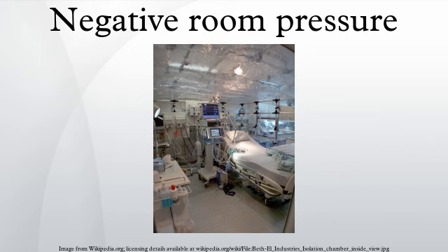If the room is at negative pressure, the smoke will travel under the door and into the room. If the room is not at negative pressure, the smoke will be blown outward or will stay stationary.